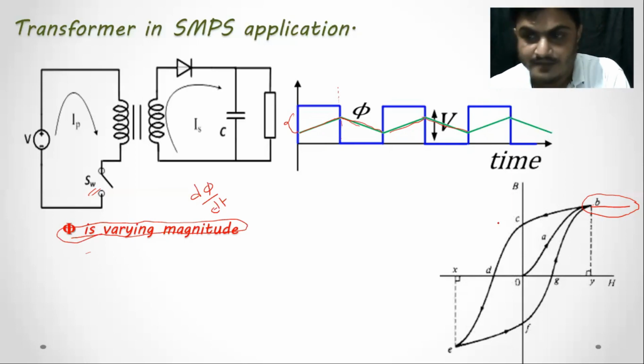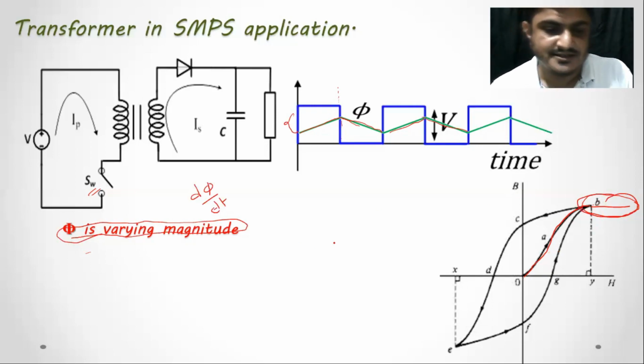So though I am saying that when a transformer is connected with DC supply, for a few microseconds it operates in a very safe region. But if you have a power transformer and cannot remove the supply within some milliseconds, the transformer will get damaged. So remember, don't try this at home. Only Rajnikant sir can have the power to disconnect the supply that fast.